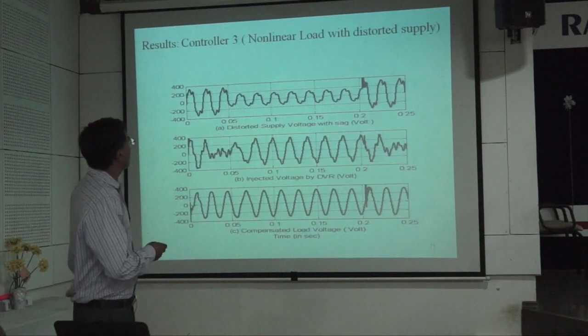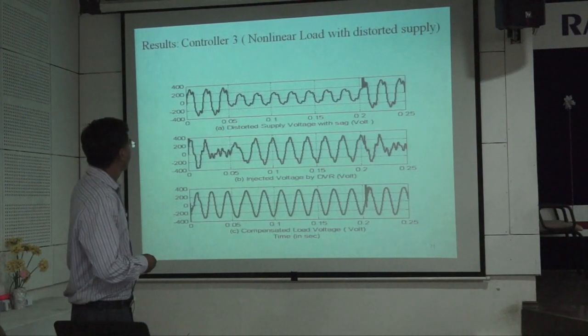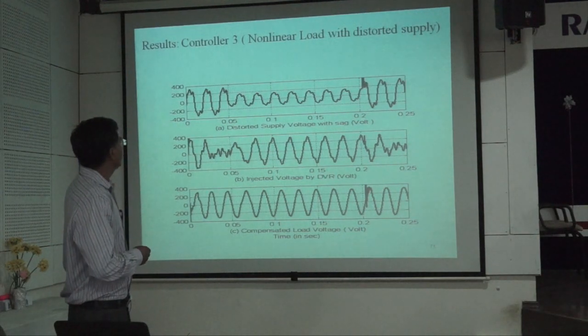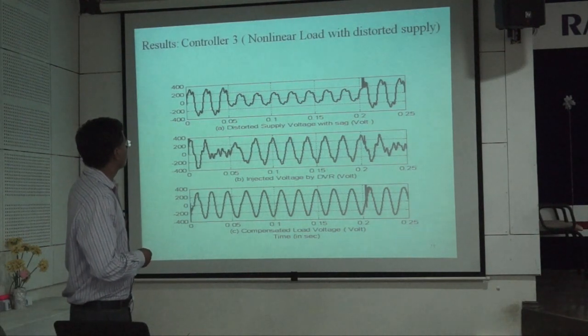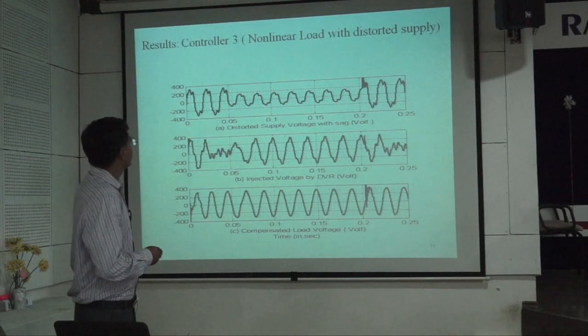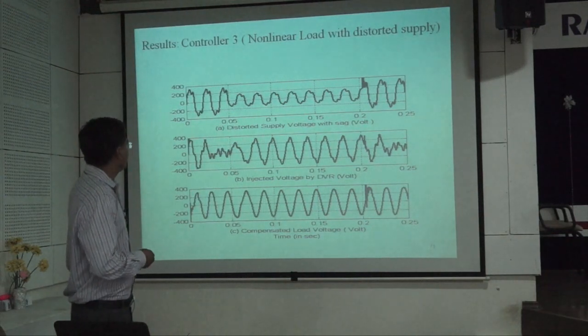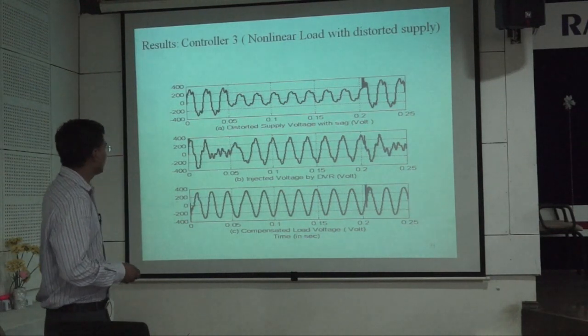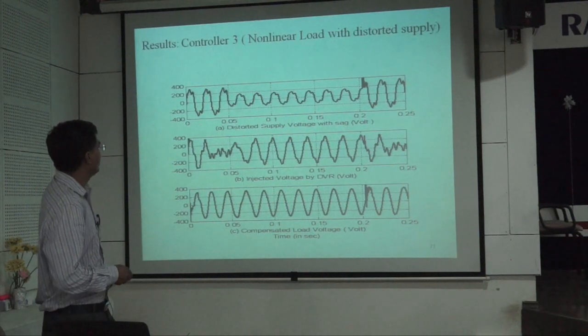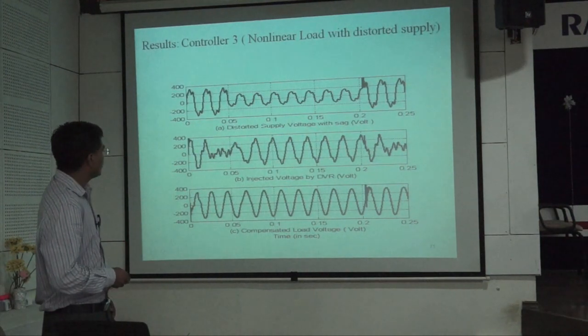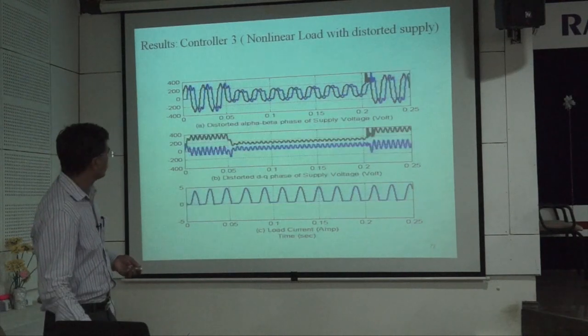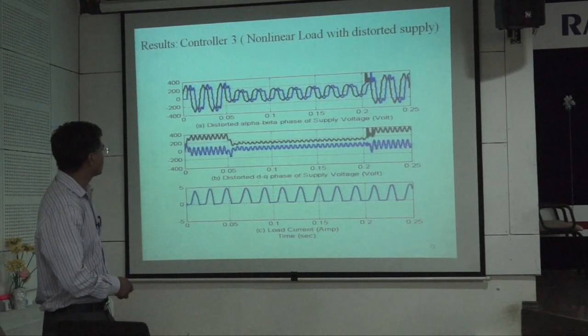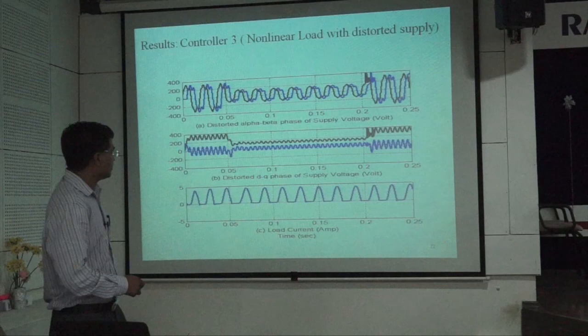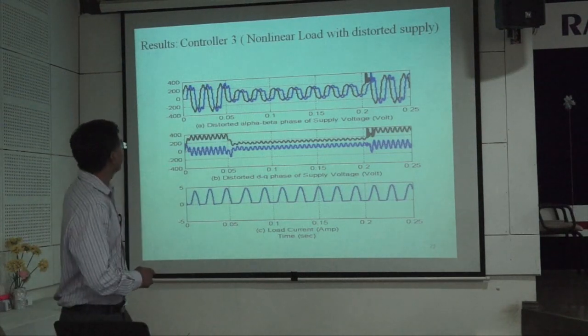Now this is for non-linear load with distorted supply. Again, the sag is created for around 7 cycles from 0.05 second to 0.2 seconds. This is the injected voltage by DVR. This is the compensated load voltage. Load voltage is maintained at the desired value. Phase is maintained. Magnitude is maintained at a constant value. These are the non-linear nature. It can be observed that the load is non-linear in nature.